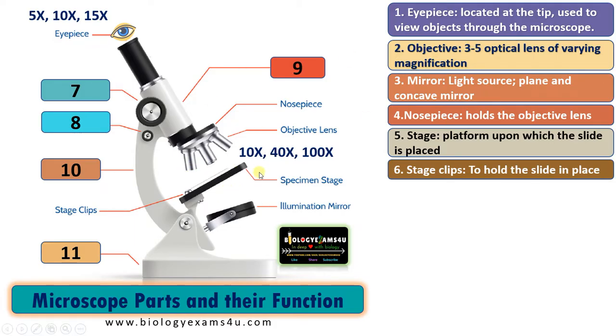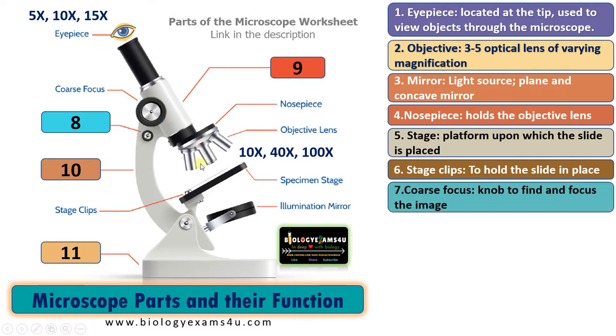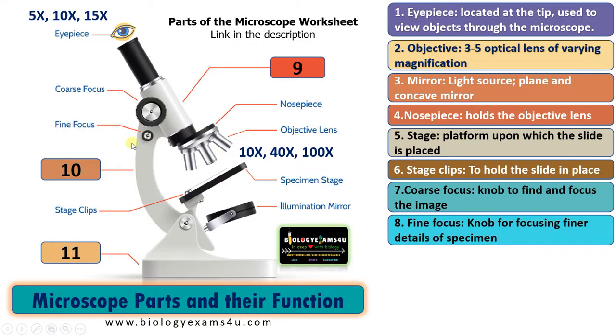Once we have placed the specimen on the stage, we will be viewing through the eyepiece using low power. Then we will use the coarse adjustment — this big knob that is rotated moves the body tube up and down to find a focused image. This is followed by the fine adjustment, or fine focus. The fine focus knob helps to focus sharper or for focusing finer details of the specimen. After fine focus, we can rotate the nosepiece to the next power to see the object at a much better magnification.